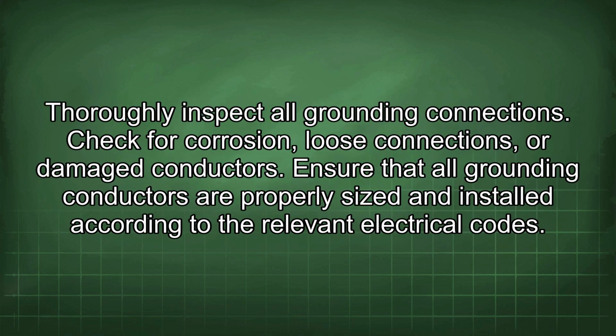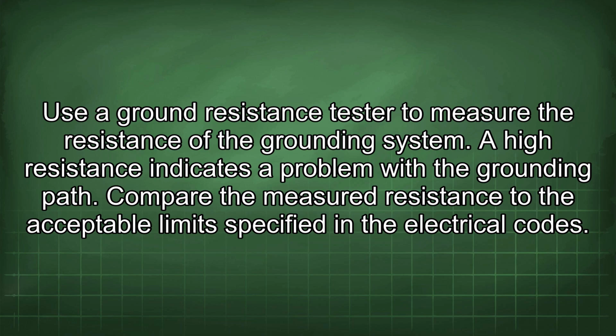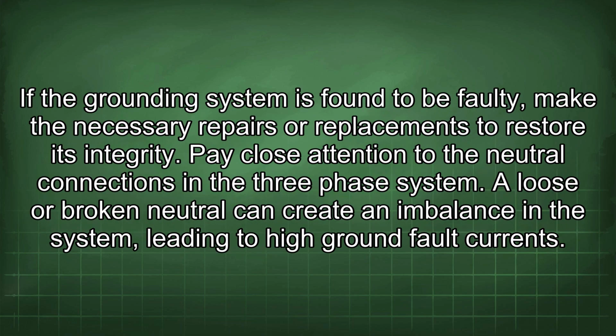Thoroughly inspect all grounding connections. Check for corrosion, loose connections, or damaged conductors. Ensure that all grounding conductors are properly sized and installed according to the relevant electrical codes. Use a ground resistance tester to measure the resistance of the grounding system. A high resistance indicates a problem with the grounding path. Compare the measured resistance to the acceptable limit specified in the electrical codes. If the grounding system is found to be faulty, make the necessary repairs or replacements to restore its integrity.